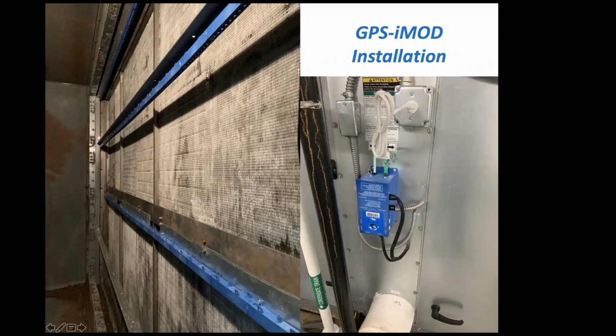Out here on the outside of the air handler, you can see how the power pack mounted, and they just plugged it into a standard outlet. You can actually cut that plug off per our UL system rating and hardwire that into your junction box if you want 24 volts or a 208 to 240.